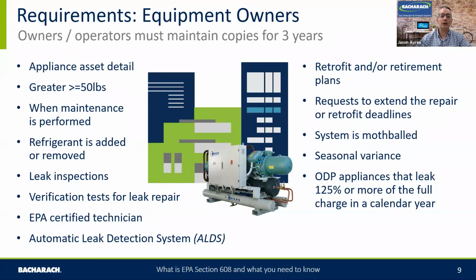First of all, the appliance and asset details need to be captured. So make, model, serial number, equipment name, date it was installed, the amount of refrigerant in the system, and the refrigerant type as a minimum needs to be captured and available. Again, just to clarify, EPA 608 is solely focused on equipment that's got over 50 pounds of refrigerant, and obviously class 1, class 2 and HFCs. That's the minimum that you have to have.